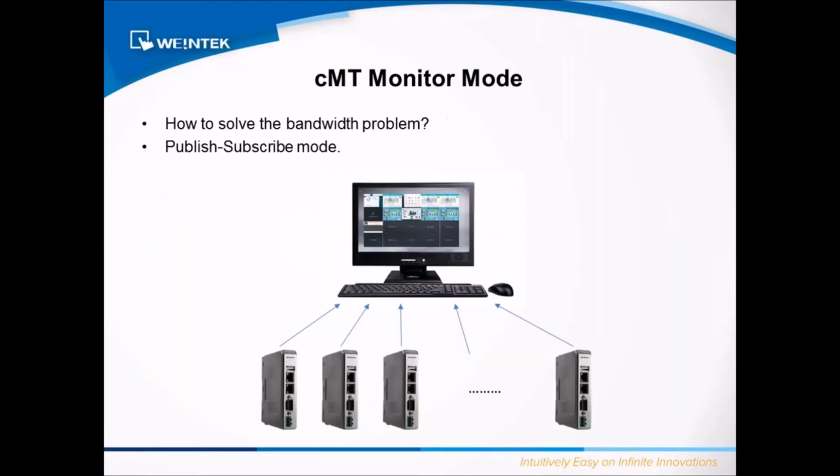Okay, so you might still be wondering, now you have this monitoring mode, but everything's still coming to this PC, right? So how do we solve the bandwidth problem? And that's with the publish subscribe mechanism, instead of what's normally used in communication, which is polling. Polling means you have to keep asking for data again and again and again, forever. With publish and subscribe mode, the data is actually updated when the actual data changes.